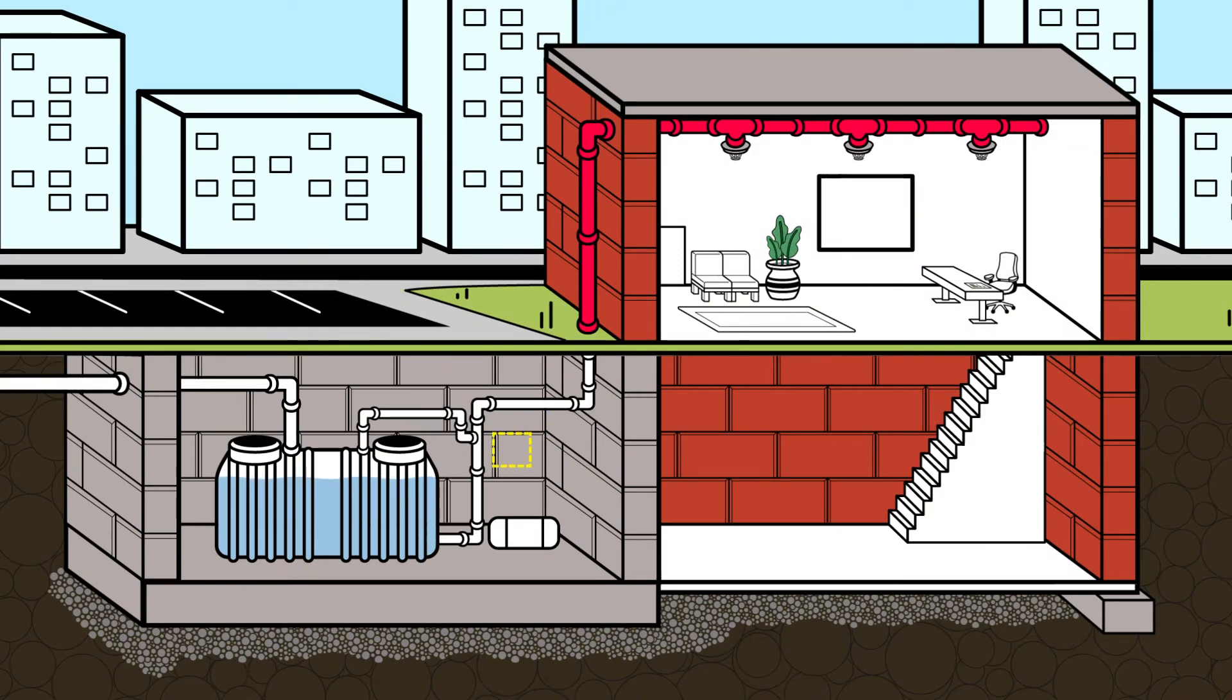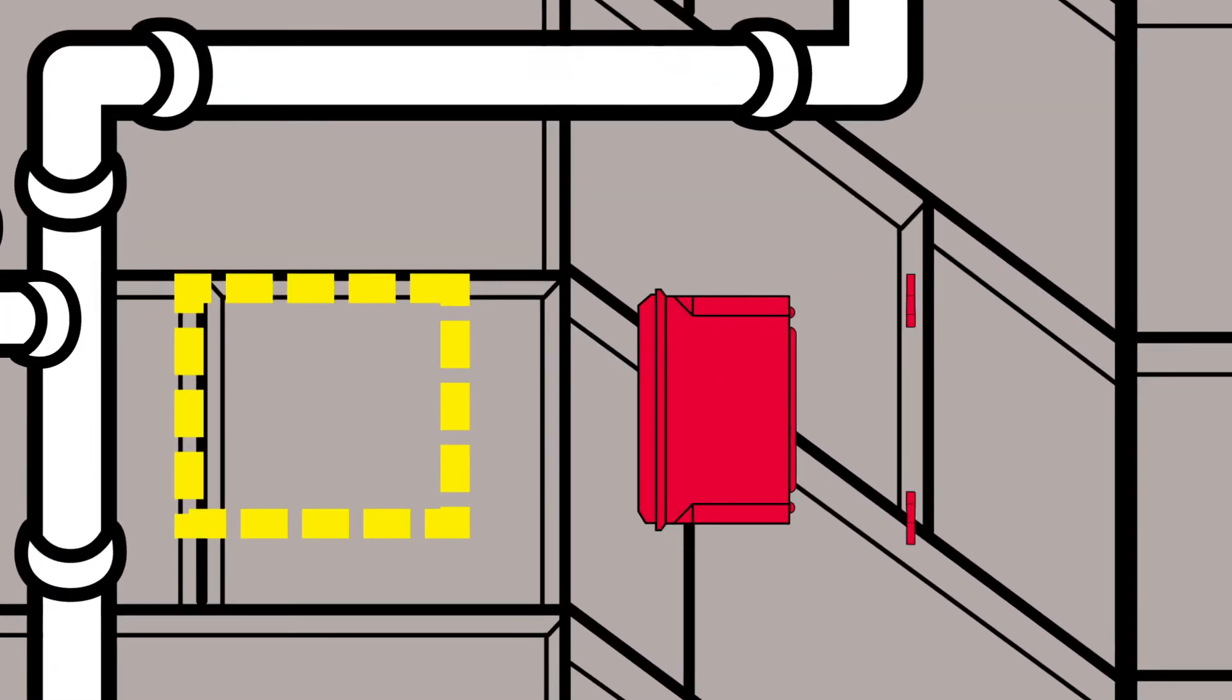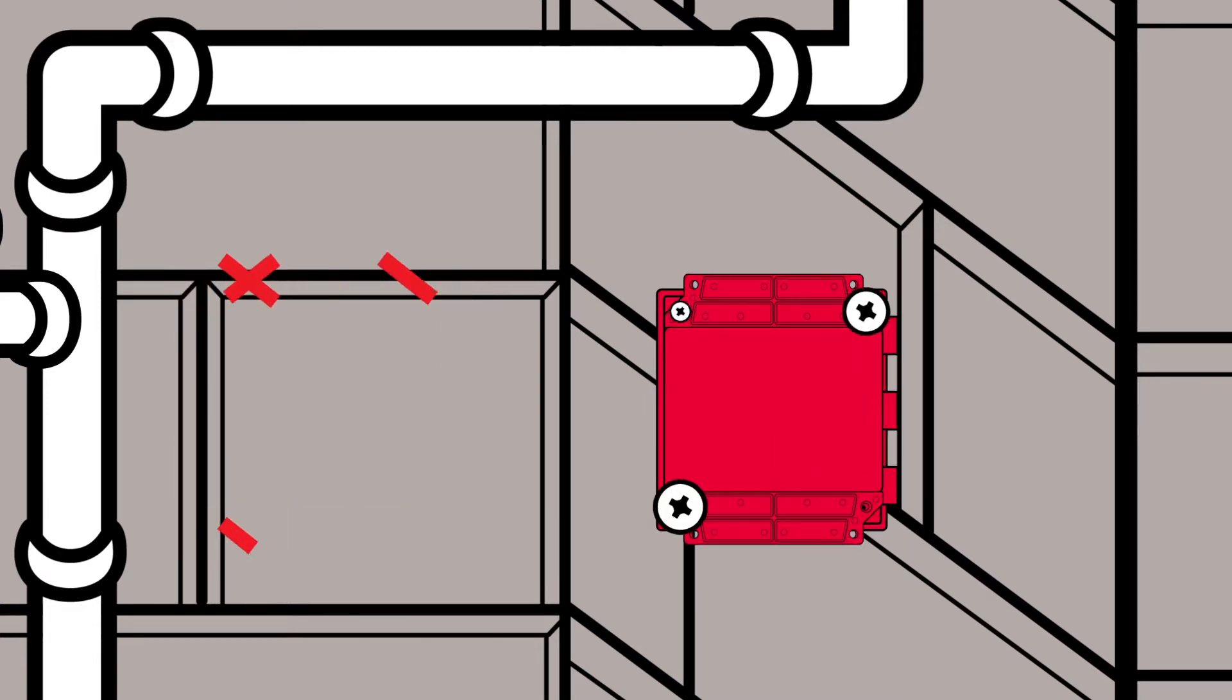We recommend placing the control panel near the tank, keeping it above the water level but out of line of sight of any VFD or DAS. The panel can be mounted on the wall using proper mounting methods for a NEMA 4X panel.